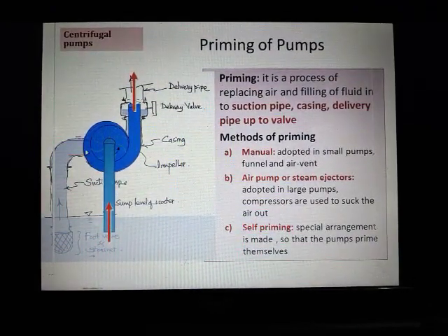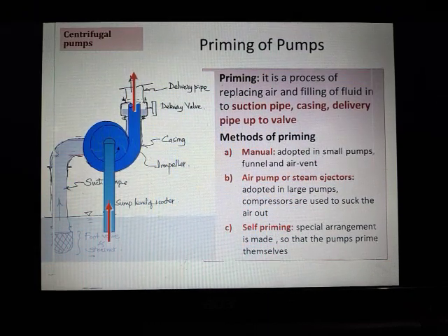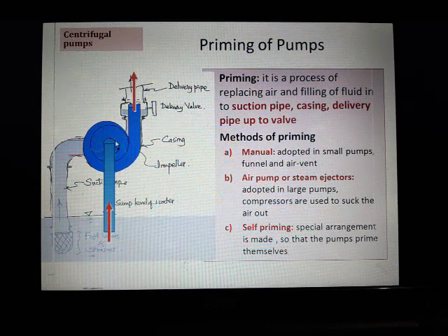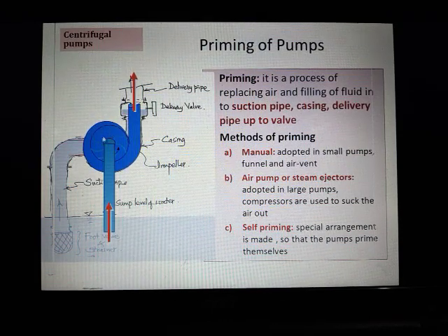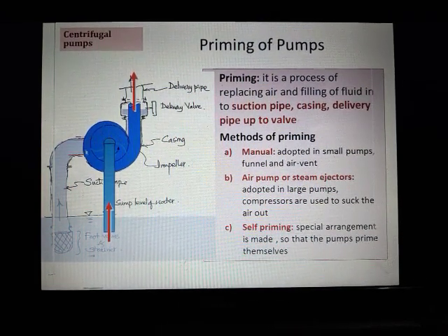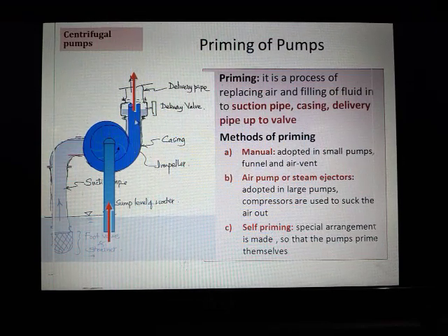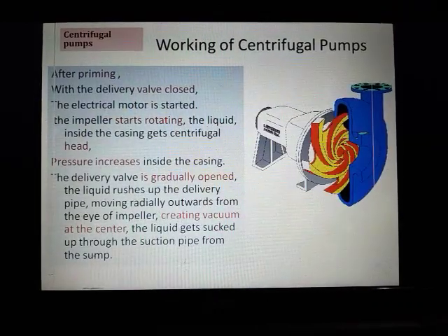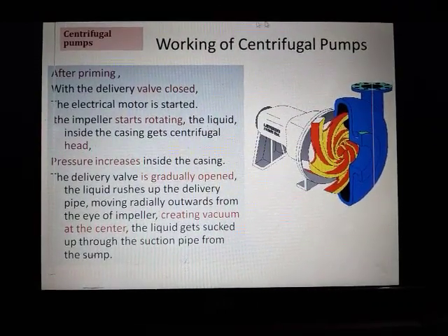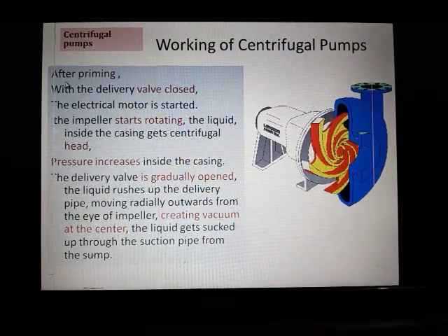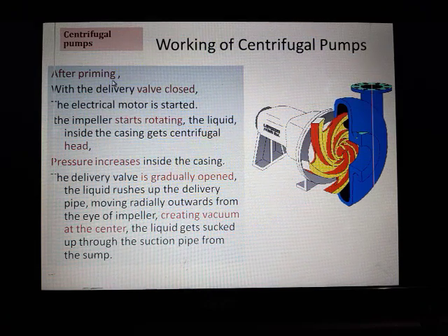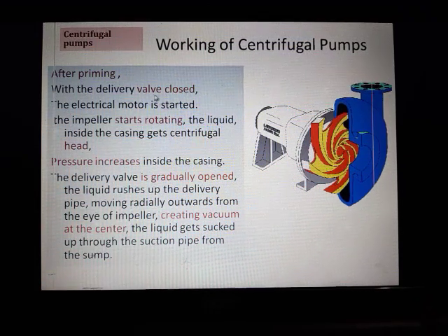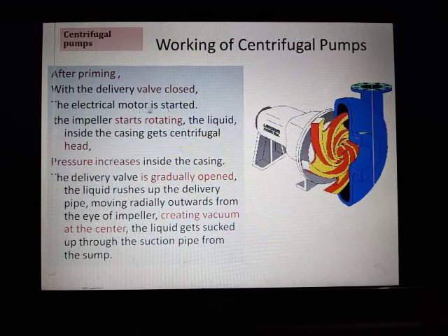The water actually enters at the centre of the impeller, and when it is rotated it gains energy and moves with more energy or pressure up the delivery pipe. Now, working of the centrifugal pump: after priming, with the delivery valve closed, the electrical motor is started.